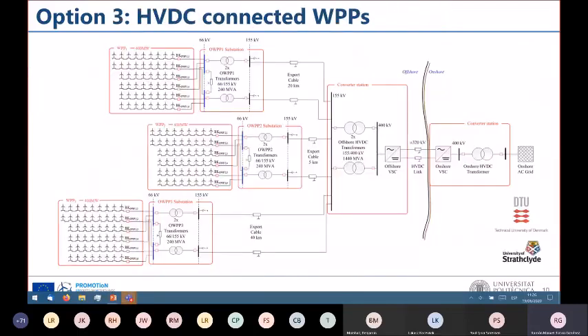The third case for black start that we have been studying in the work package is what happens when we have an HVDC connection. In this case, we have the different wind farms that are going to bring up the system, the offshore VSC station, and then the onshore VSC station. I think Nikos can correct me if I am wrong, but two cases were studied: one with intermediate substations here, and another one without the intermediate substations. So we have been covering a quite wide range of possible scenarios to carry out the blackout and the black start testing of the different controllers for the wind turbines.